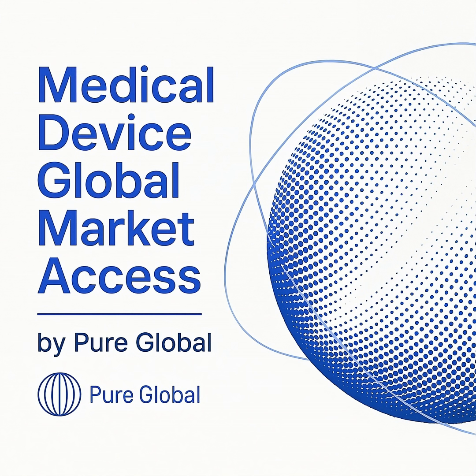The good news is that the extensive data from your PMA submission is highly valuable. Health Canada allows for the use of FDA guidance materials to support a Canadian medical device license application, a notice that was formalized on August 4, 2016. The comprehensive safety and effectiveness data, including preclinical and clinical studies, from your PMA submission can be repurposed. However, it must be presented in the format required by Health Canada, which is now aligned with the International Medical Device Regulators Forum, or IMDRF, Table of Contents structure. Your submission must explicitly demonstrate compliance with Canadian safety and effectiveness requirements.